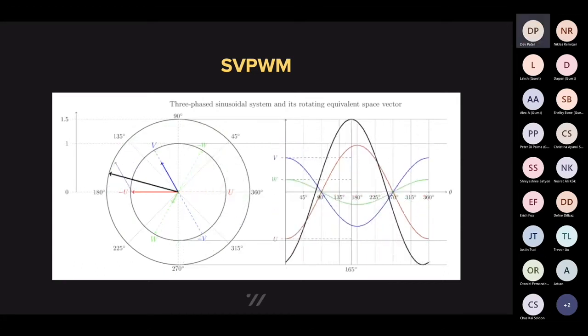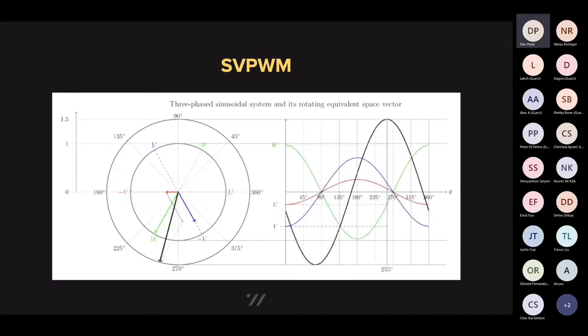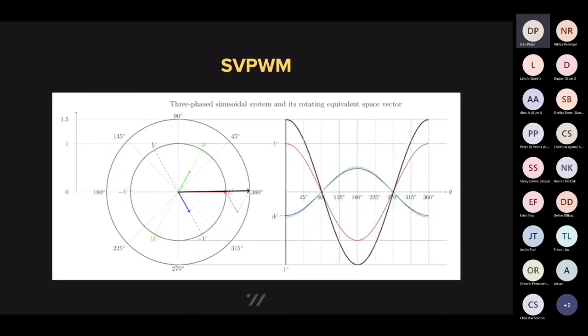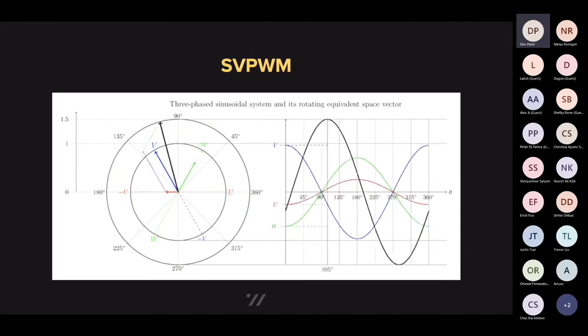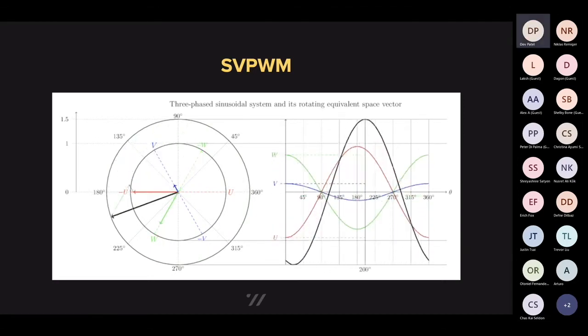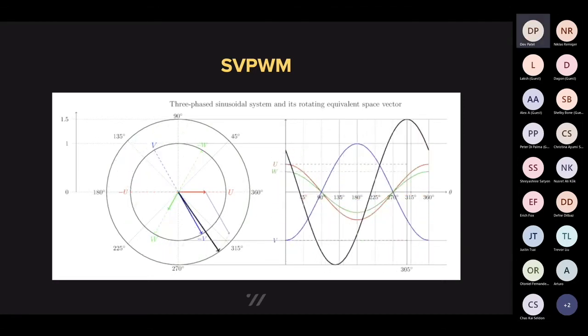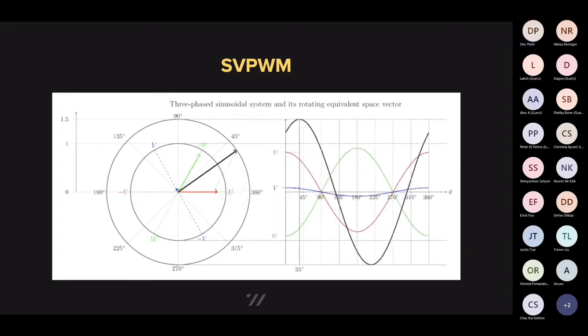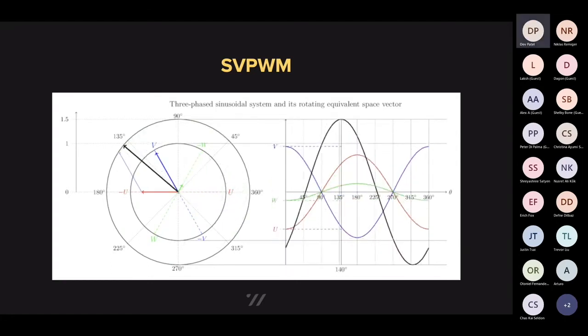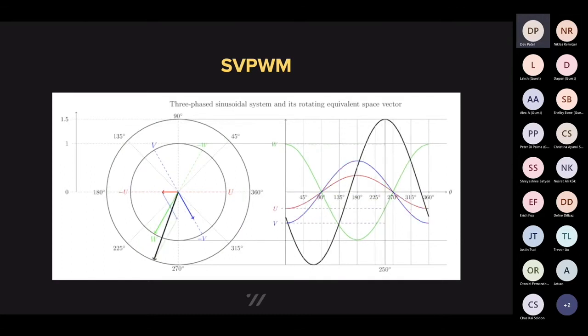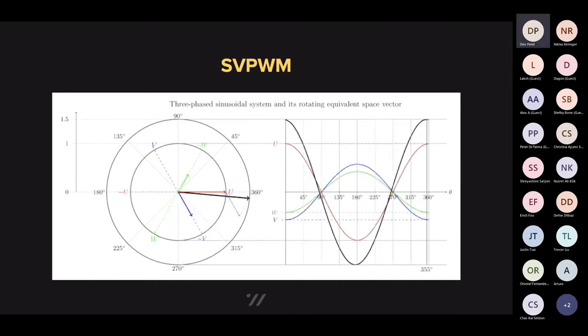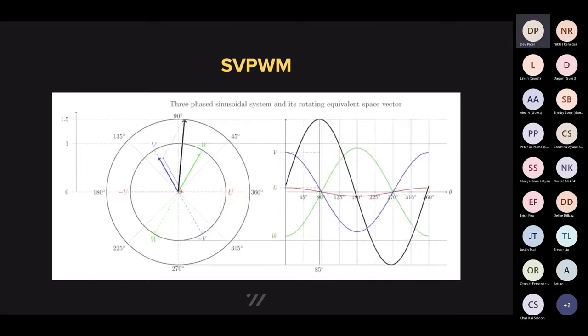SVPWM uses some basic linear algebra to determine how to switch the motor controller switches so that we can recreate a magnetic field pointing in any direction. We have to do this calculation about 10,000 times a second. This is also referred to as the switching frequency, and it can vary depending on a number of factors. This frequent switching is done to create a smooth rotating magnetic field.